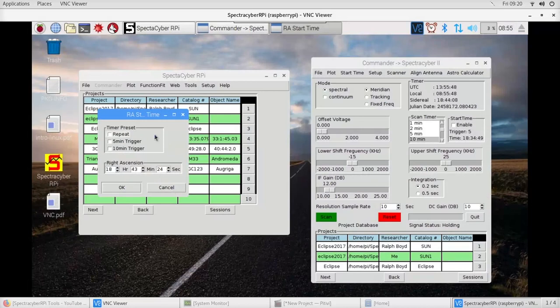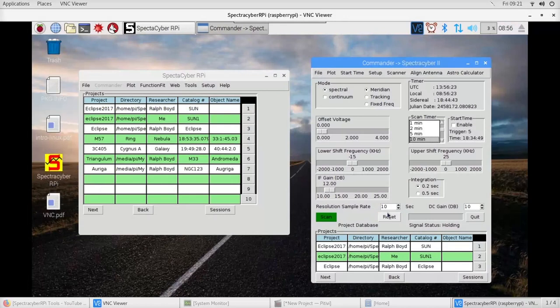And this, of course, is best used in the project mode, because the project mode will automatically set your data and save your data for you. If you were to do it in the user mode, it would simply be overriding yesterday's previous scan in the temporary file. So it's really more functional to use this in the project mode. That's what it's intended for. This gives you a completely unattended mode. Set this up, make it repeat, come back a week later, and you will have a lot of data waiting in your project file.